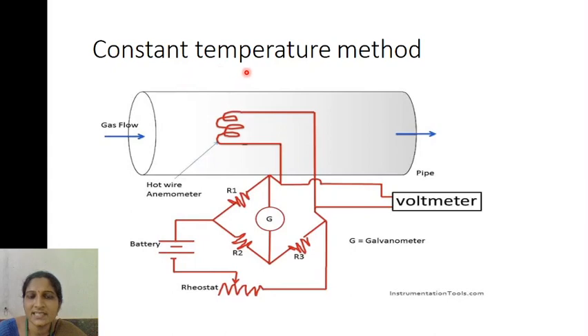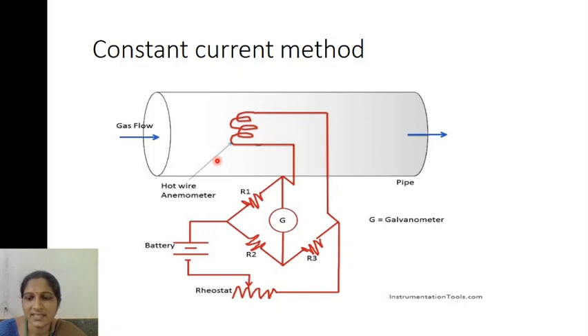Likewise, in the constant temperature method, you maintain the temperature as constant. To maintain the temperature constant, you need to supply more and more current to the hot wire anemometer. The flow to be measured is flowing in this pipe, and the temperature tries to change. To make the temperature constant, by using this rheostat you increase or decrease the current to maintain the constant temperature. When there is any deflection, that indicates there is some gas flow, which is measured by using the galvanometer here. So this is the hot wire anemometer for the measurement of flow using the constant temperature method and the constant current method.